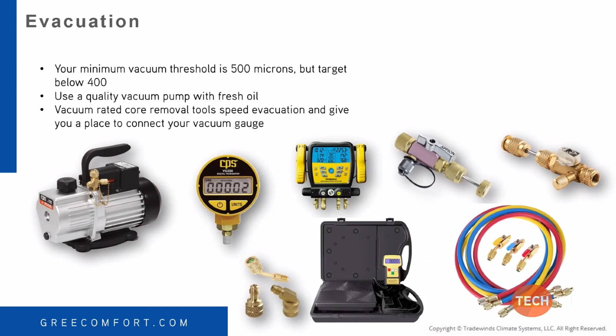Now, evacuation. The minimum vacuum that we want to pull it down to is not 30 inches of mercury on your gauge. We want to use an actual micron gauge, and we want to pull it down below 500. We always want to make sure we've got a good vacuum pump with clean oil.